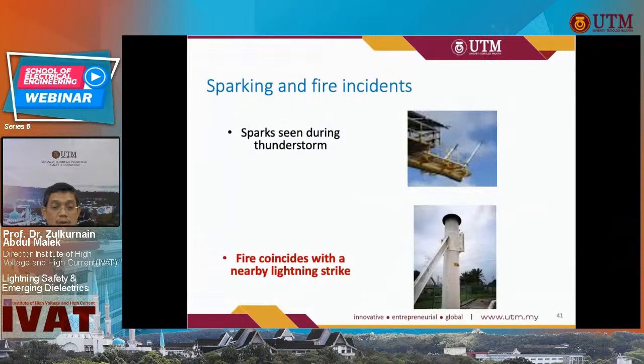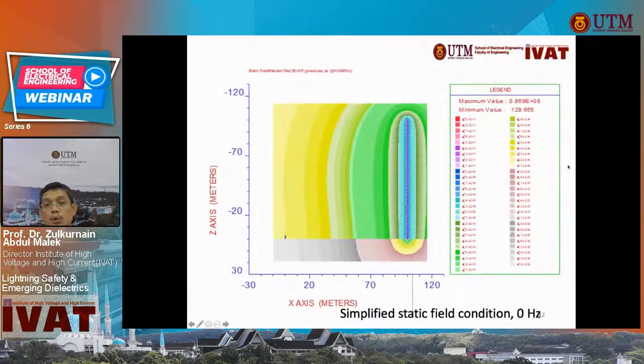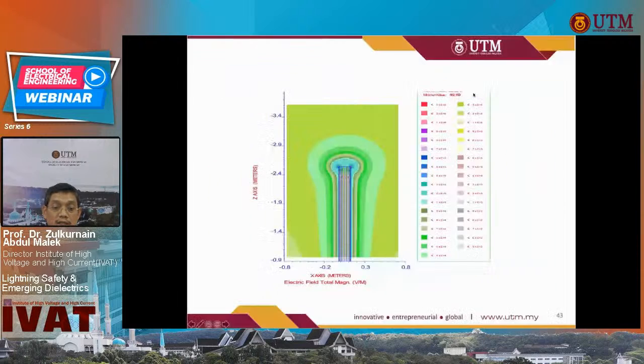Okay, as proof of it, they have seen sparks during thunderstorms as well as fire when there is a nearby lightning strike. So our theory is that even though it's quite far away, the vent stack can also have an upward leader discharge at the edges, and this upward streamer has enough energy to actually ignite flammable gas. So we simulated a very large current flow and a very large voltage, a massive electric field, and our vent stack, quite 100 meters away, can actually have an electric field induced at the edges typical of a breakdown voltage, which is 30 kV per centimeter. So this proves that the edges can produce corona due to the nearby leader.